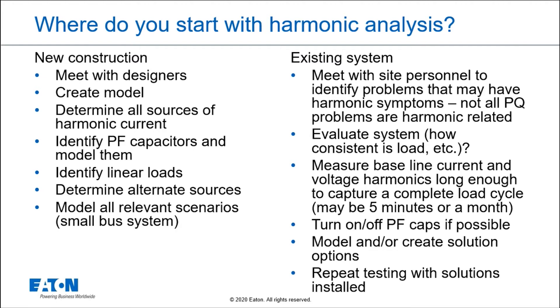So then we want to evaluate the system — how consistent is the load? Are we going to be able to do measurements and determine what that load is all the time? Then we want to take baseline measurements, and those baseline measurements could be five minutes to a month. It depends on what is one complete load cycle of the power system, so we understand what the harmonics look like at a very heavy load, at a light load, peak and off peak, and so forth. We want to be able to turn on and off power factor correction capacitors if we can, to determine if resonant points are problematic.